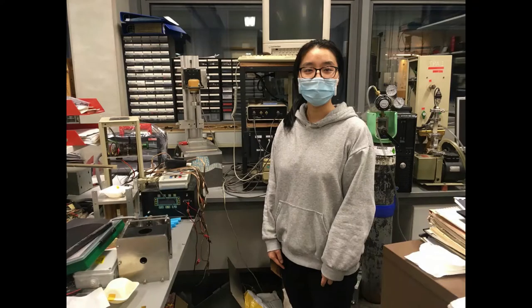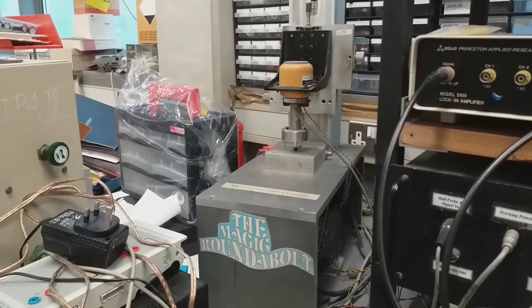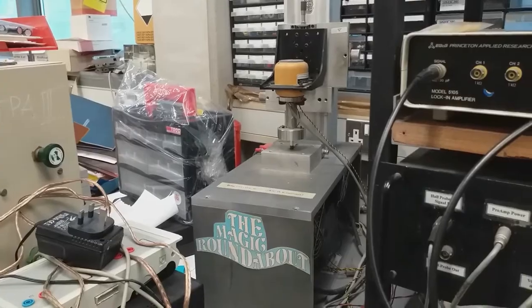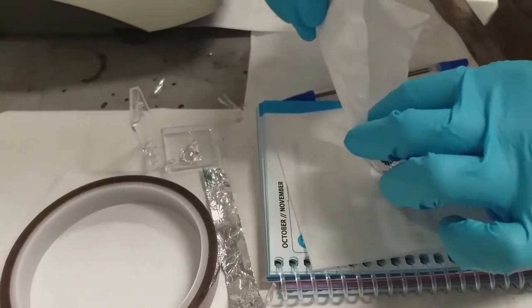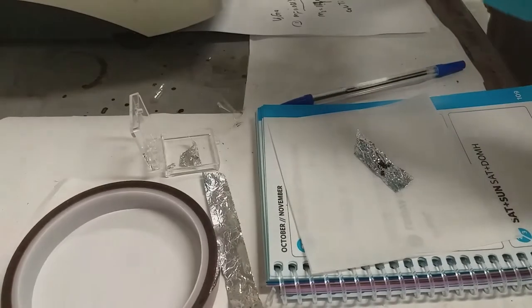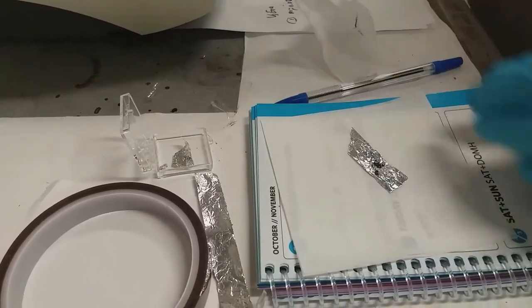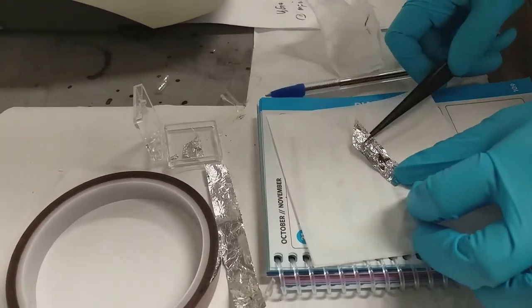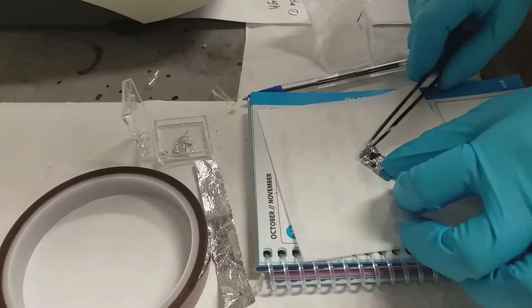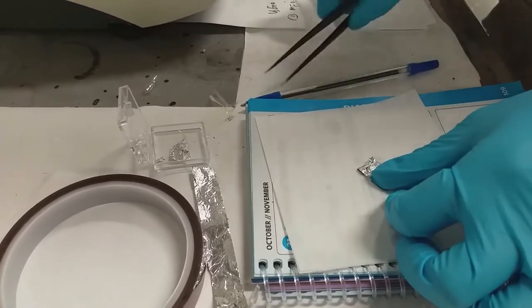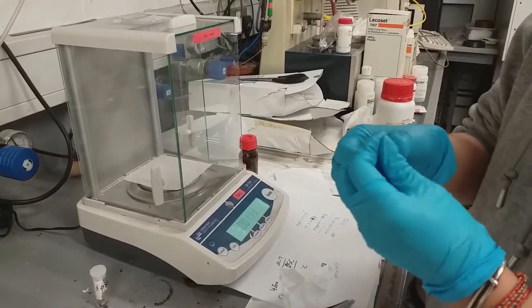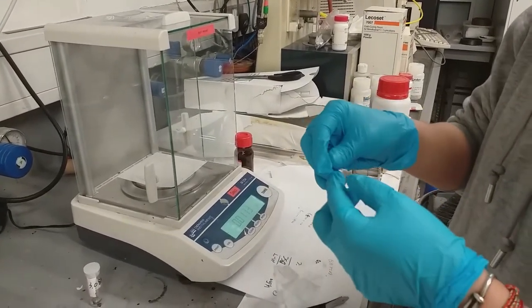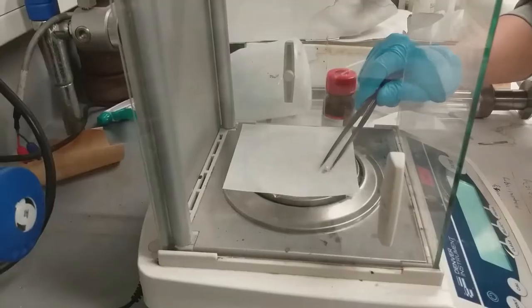Hello, my name is Ray Zhang. I'm a PhD student in this group. This is the main part of the VSM instrument which provides a magnetic field. The VSM can measure powder, bulk, or liquid samples. One thing we have to notice is how to prepare a proper sample to load. It requires a tightly packed sample. Here, we use aluminum foil which is non-magnetic to pack the sample.